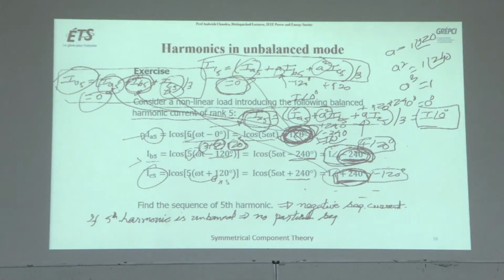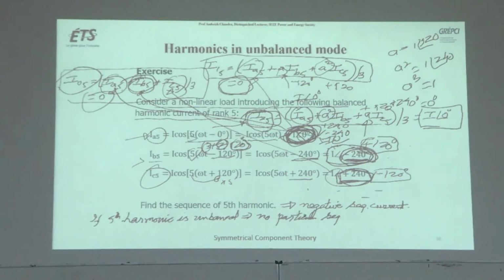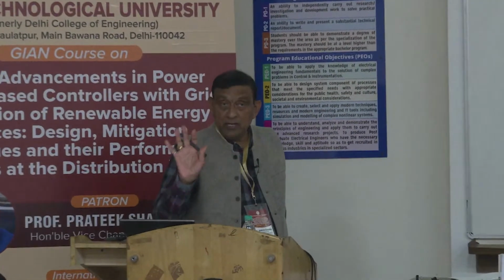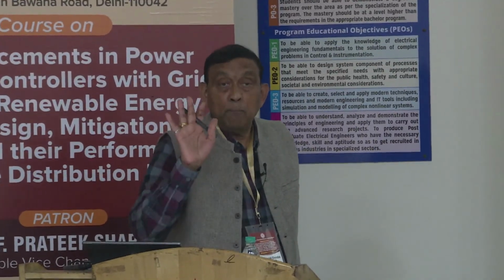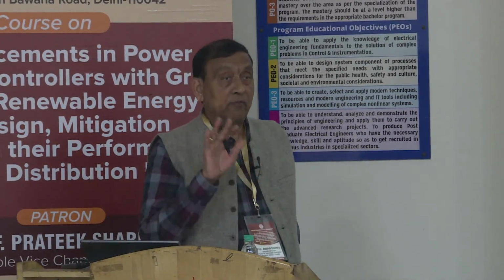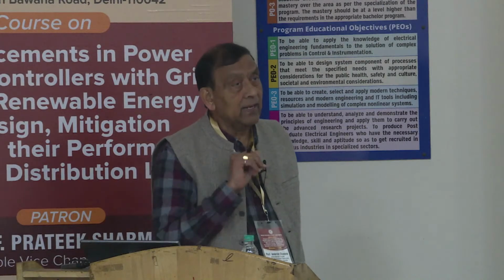If the fifth harmonic is balanced, this is the condition. If the fifth harmonic is balanced, then only it has a particular sequence. If the fifth harmonic is unbalanced, then it will have zero sequence also, it will have negative sequence, it will have positive sequence. But here we are talking about the balanced fifth harmonic. If the fifth harmonic is balanced, it has the negative sequence.